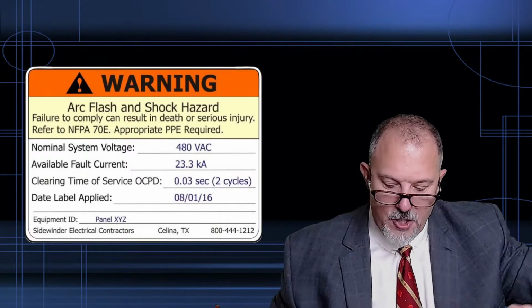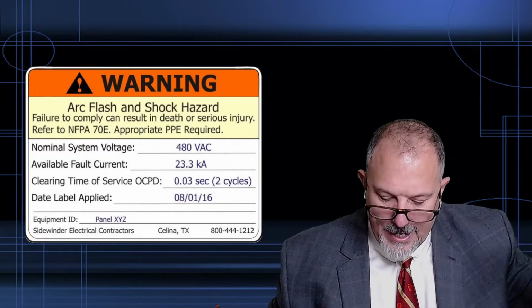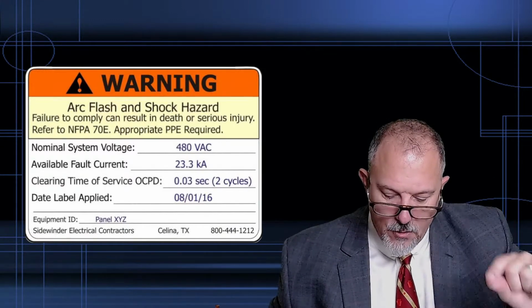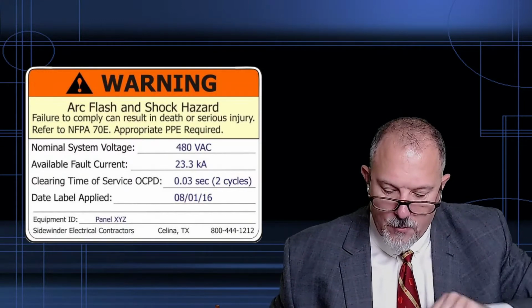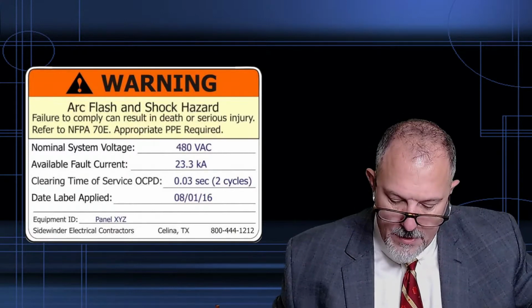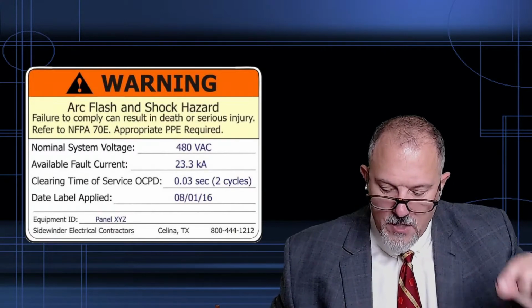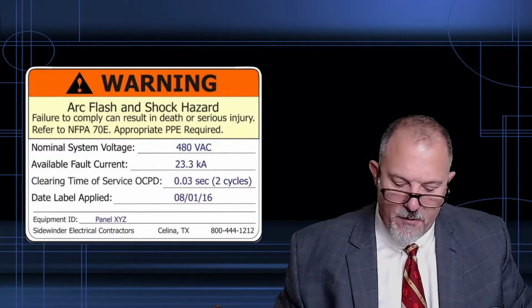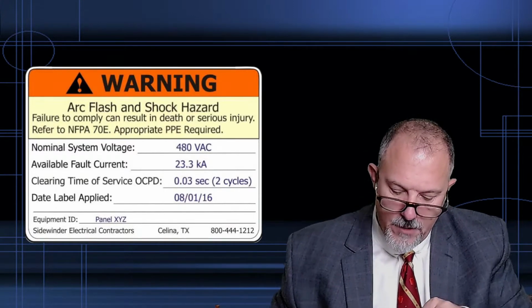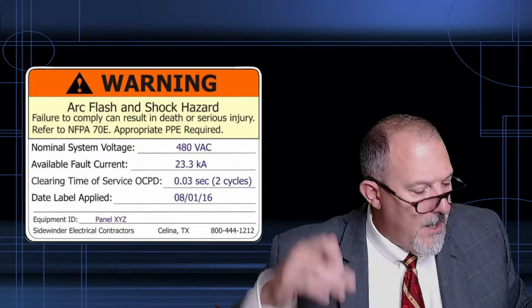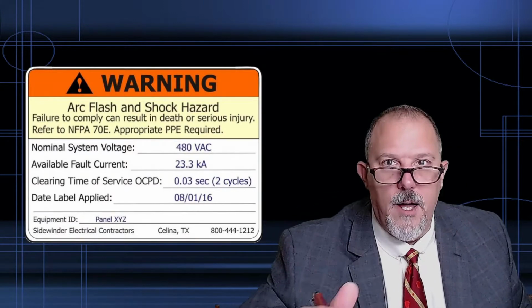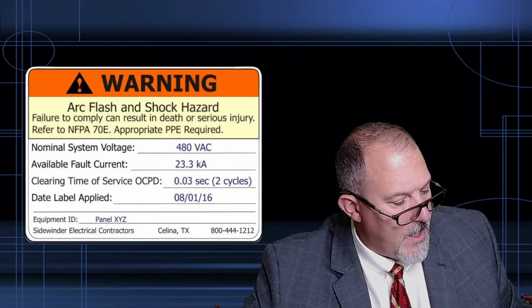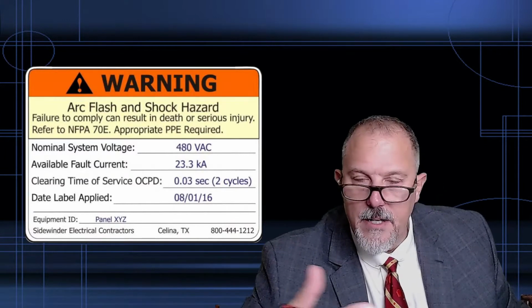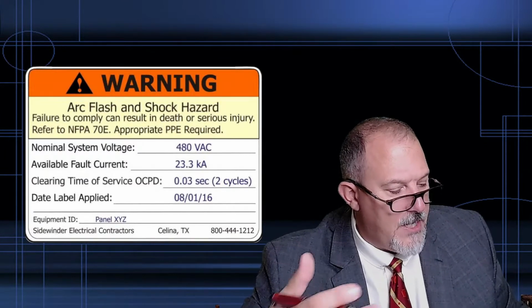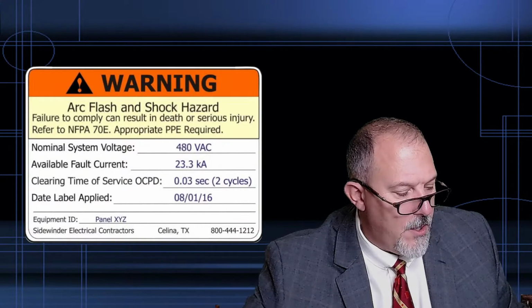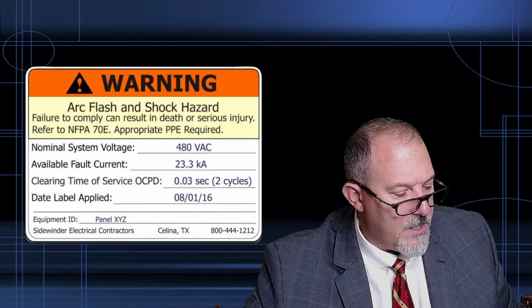In other than dwelling units, in addition to the requirements in A, a permanent label shall be field or factory applied to service equipment rated 1200 amps or more, and the label shall meet the requirements of 110.21(B) and contain the following information: nominal system voltage, available fault current, and so on. And there are 3 informational notes talking about 70E and Z535 and acceptable industry practices for labeling.